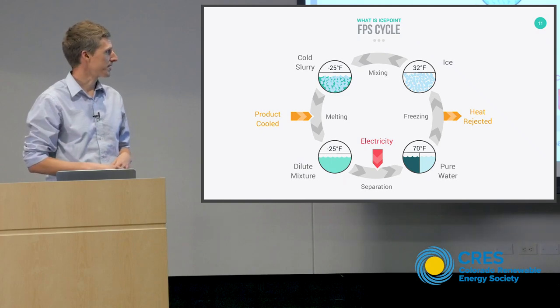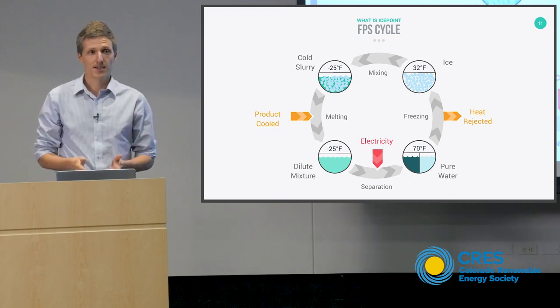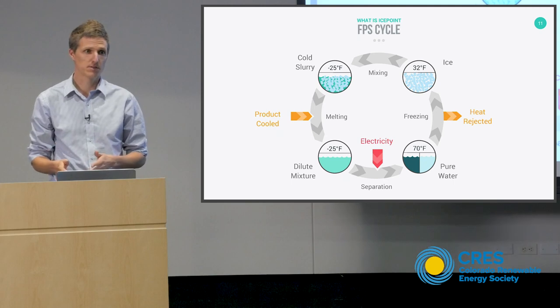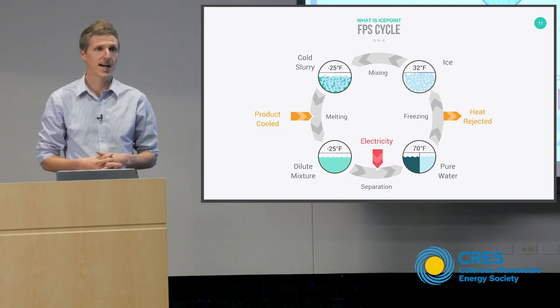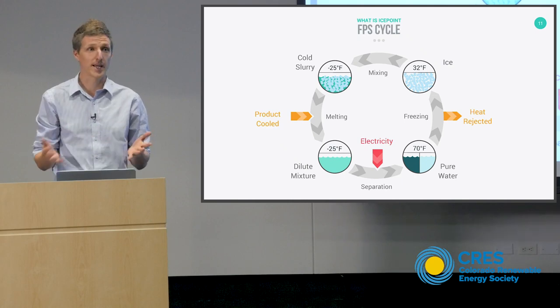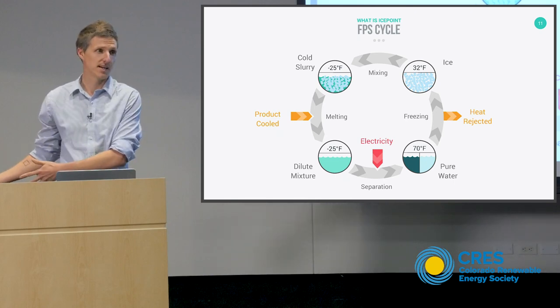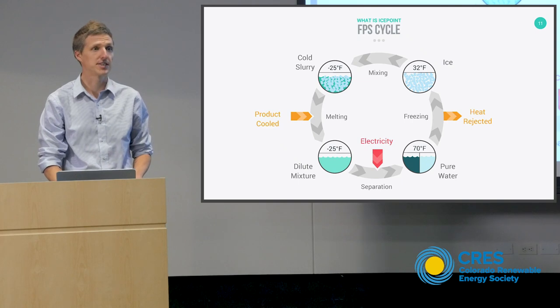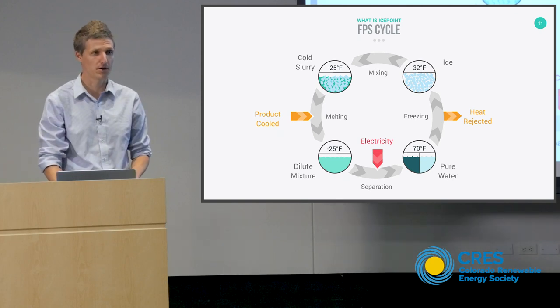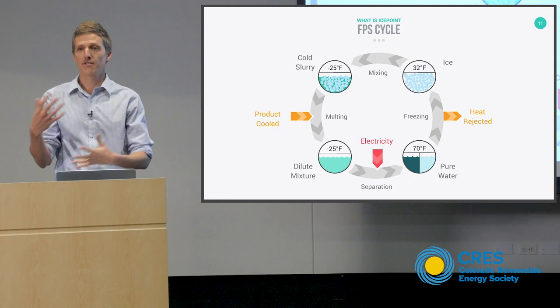Just like a vapor compression cycle, we're just running around the cycle. Water is our refrigerant and we use a salt brine — not table salt, but a mixture of salt with a lower freezing point — to drop that temperature. While the thermodynamics are very similar, the important distinction is that all of our processes are inherently storable. Nothing we're doing is at an extreme pressure or extreme temperature. We can take each of these states and put them in a giant plastic tank and wait as long as we want. Imagine if we made a bunch of ice — we could put it in an insulated tank and wait a day before we mixed it with the brine.